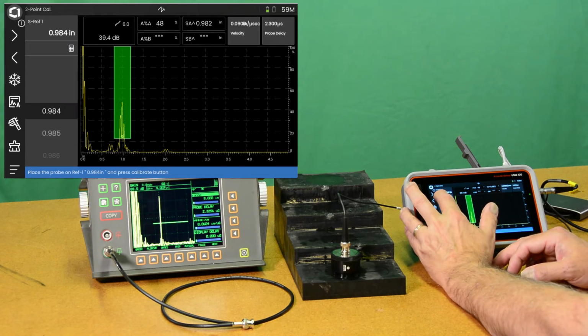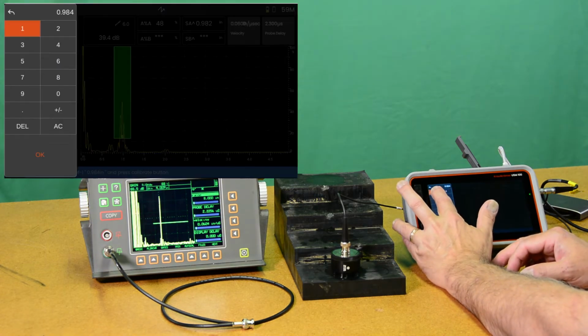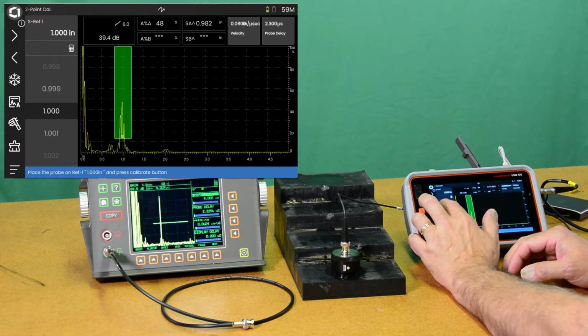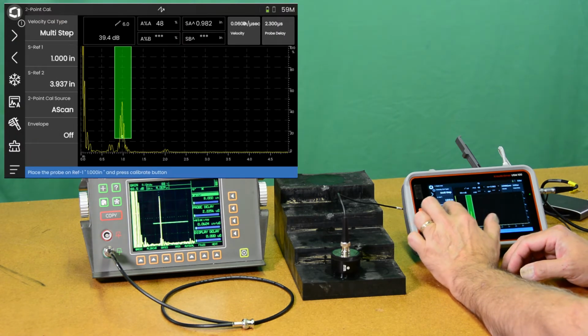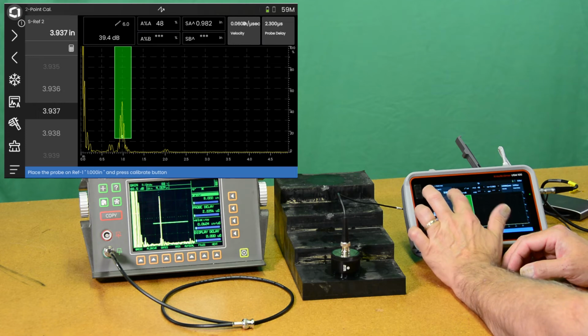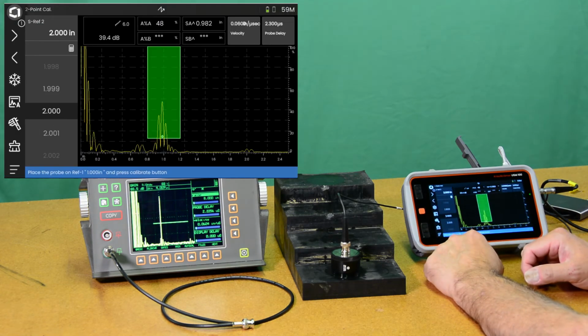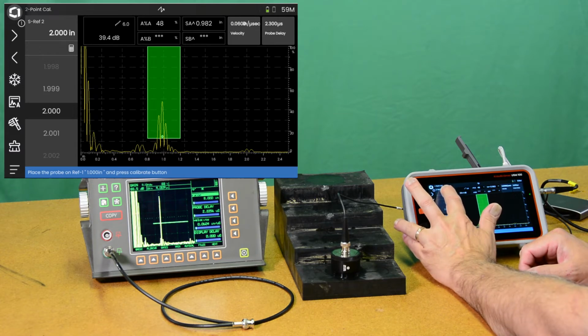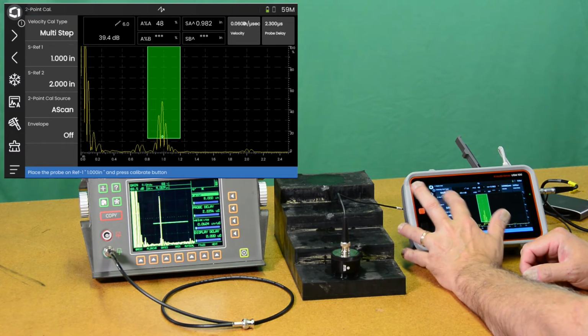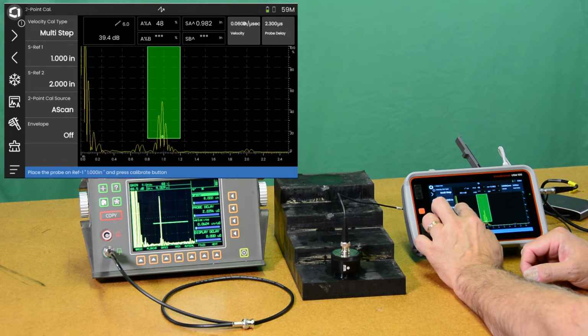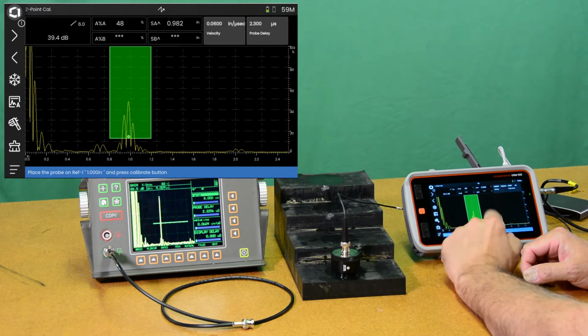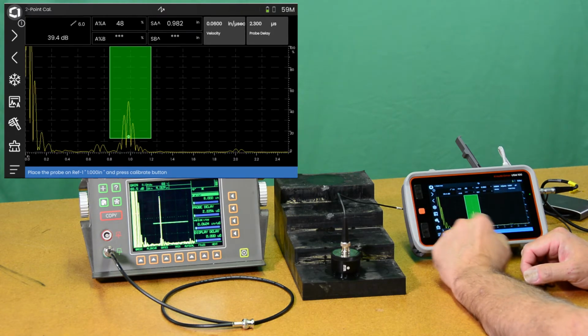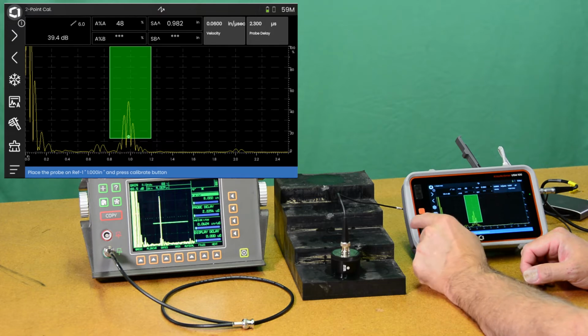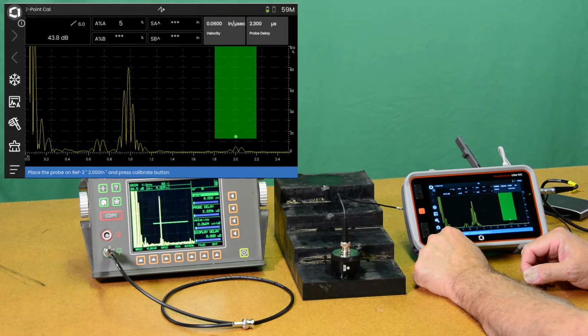So the two of the most frequently used controls are going to be our reference 1 thickness. What's the thickness of the first step we're going to look at, and what's the thickness of the second. So we're going to tell it we want to look at 1 inch and 2 inch. Okay, and we're going to do multi-step calibration, so I can swipe left to hide that menu again. My gate is already over my 1 inch echo. I can do auto 80 and hit calibration.